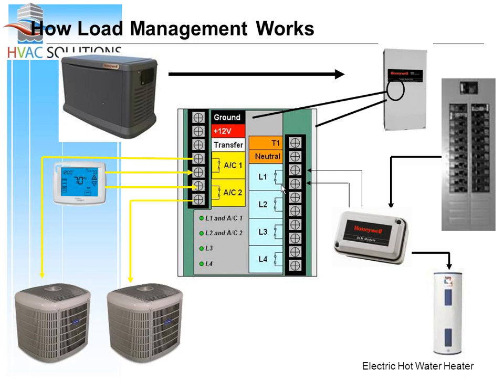On the L1, L2, L3, and L4, I want to talk about two different things because we are right smack dab in the middle of model number changes. So older transfer switches, this side is going to be a 110-volt circuit. So in that case, you need a DLM module. And that's that little box right in between the circuit board and the customer circuit breaker box. And really what that is, is a 50 amp contactor. It's allowing us to either open or close that circuit based on what the L1 through L4 is telling it to do.